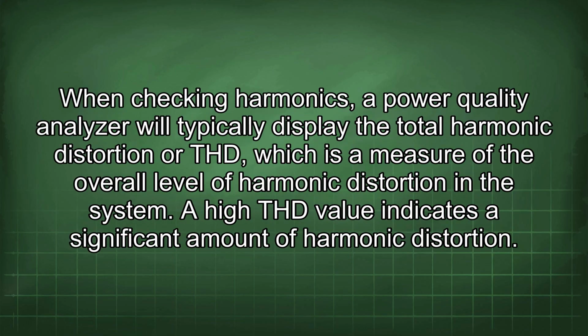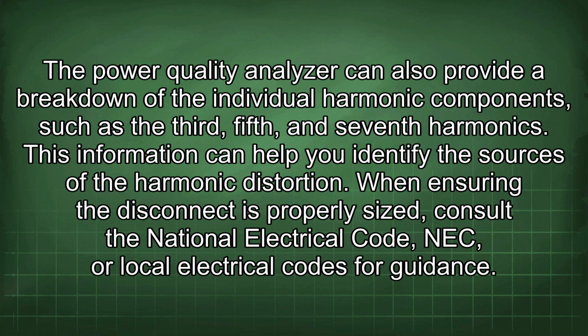When checking harmonics, a power quality analyzer will typically display the total harmonic distortion, or THD, which is a measure of the overall level of harmonic distortion in the system. A high THD value indicates a significant amount of harmonic distortion. The power quality analyzer can also provide a breakdown of the individual harmonic components, such as the third, fifth, and seventh harmonics. This information can help you identify the sources of the harmonic distortion.